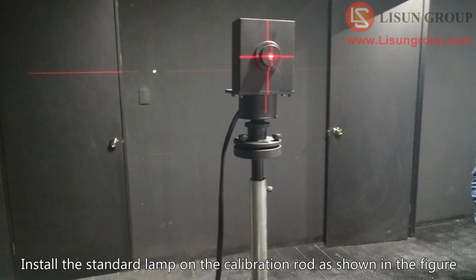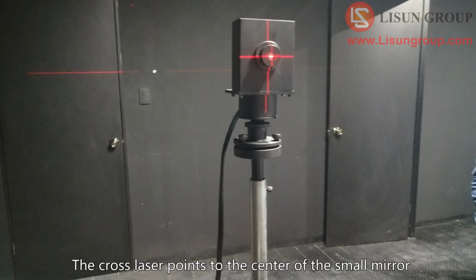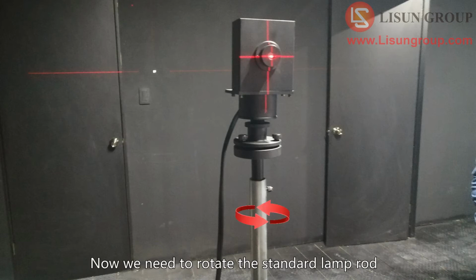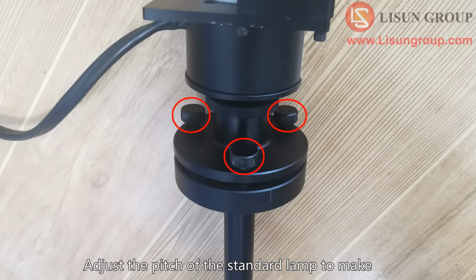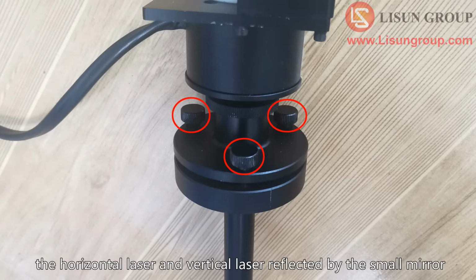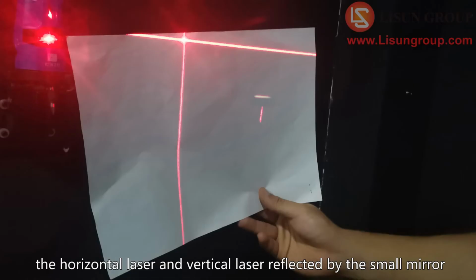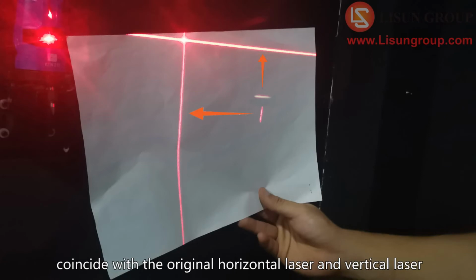Install the standard lamp on the calibration rod as shown in the figure. The cross laser points to the center of the small mirror. Now we need to rotate the standard lamp rod. Adjust the pitch of the standard lamp to make the horizontal laser and vertical laser reflected by the small mirror coincide with the original horizontal laser and vertical laser.